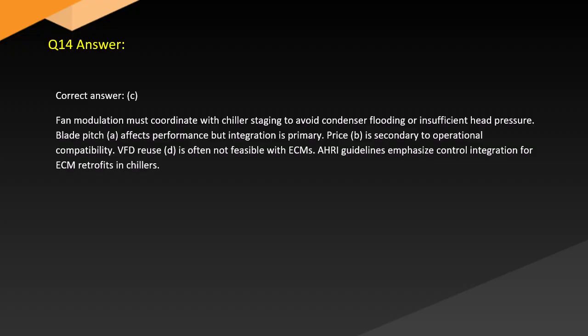Answer. Correct answer: C. Fan modulation must coordinate with chiller staging to avoid condenser flooding or insufficient head pressure. Blade pitch, A, affects performance, but integration is primary. Price, B, is secondary to operational compatibility. VFD reuse, D, is often not feasible with ECMs. AHRI guidelines emphasize control integration for ECM retrofits in chillers.